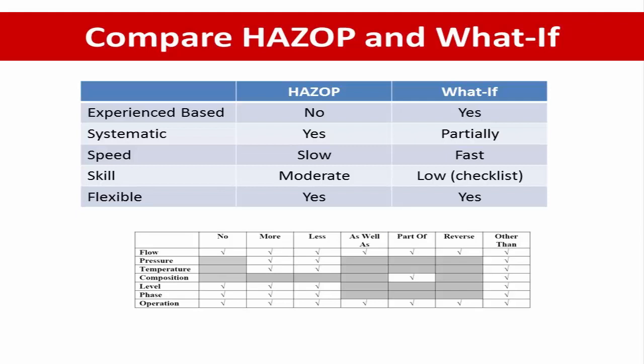HAZOP does not require experience-based knowledge because standard guide words guide the participants in the meeting. What If does require it, because otherwise questions in the meeting will be fully open and difficult to close. Systematic: HAZOP is very systematic; What If is only partially systematic. Speed: HAZOP is very slow because there are many guide words to study; What If is fast to implement. Skills: HAZOP requires a moderate level; What If may require low skill if combined with a checklist. Flexibility: both studies are flexible for any stage of engineering, but HAZOP is normally mandatory during detailed engineering.